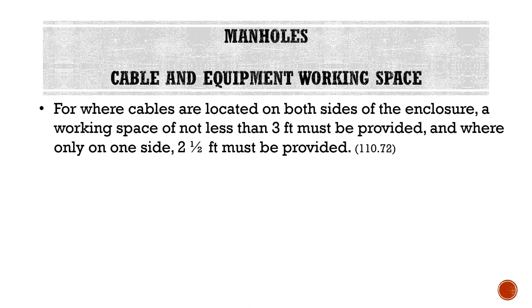Regarding cable and equipment working space within manholes: where cables are located on both sides of the enclosure, a working space of not less than three feet must be provided. Where cables are only on one side, a working space of two and a half feet must be provided. We're always going to need some type of working space inside a manhole in order to safely work while inside it.